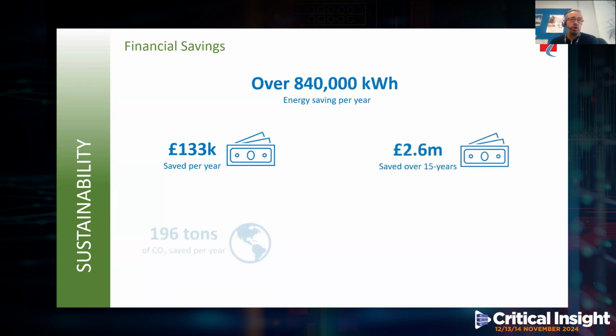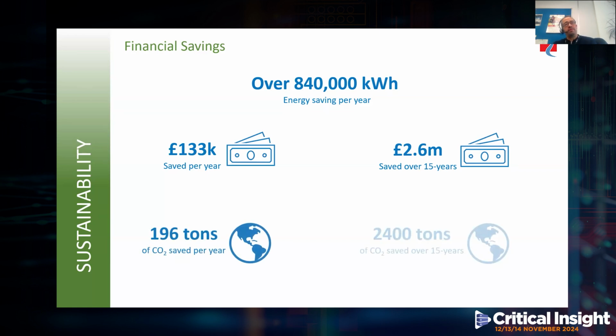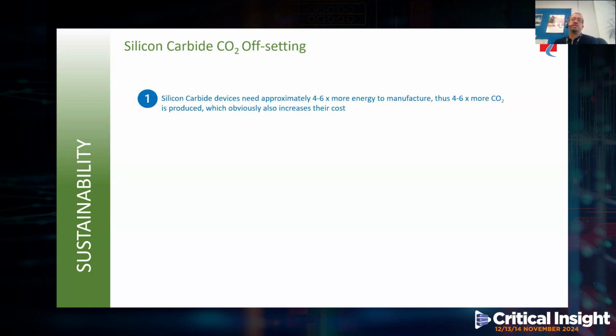Now, in terms of the environment, over 196 tons of CO2 are saved per year. And over 15 years, this adds up to over 2,400 tons of CO2 saved. And so, as you can appreciate, the savings are significant, and obviously they simply cannot be ignored. Now, it goes without saying, obviously, that silicon carbide may appear to be the miracle cure, but there is obviously a key point that I need to cover. Silicon carbide devices need approximately 4 to 6 times more energy to manufacture. Thus, 4 to 6 times more CO2 is produced, which obviously also increases their production costs.